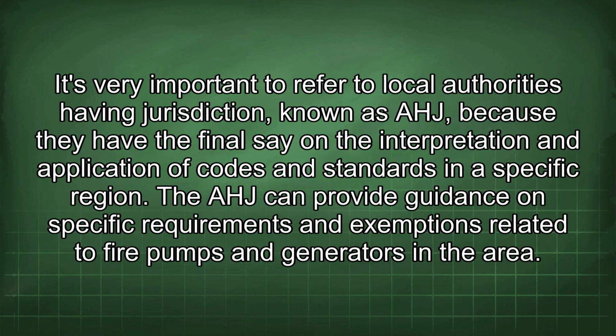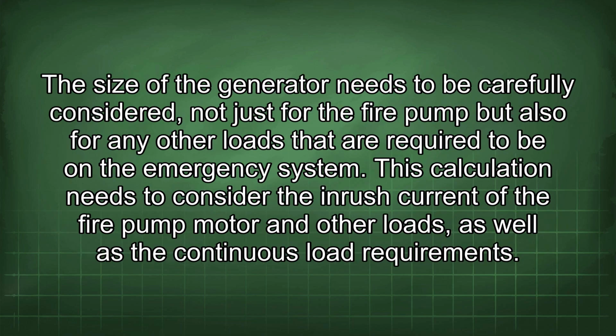It's very important to refer to local authorities having jurisdiction, known as AHJ, because they have the final say on the interpretation and application of codes and standards in a specific region. The AHJ can provide guidance on specific requirements and exemptions related to fire pumps and generators in the area. The size of the generator needs to be carefully considered, not just for the fire pump but also for any other loads that are required to be on the emergency system.